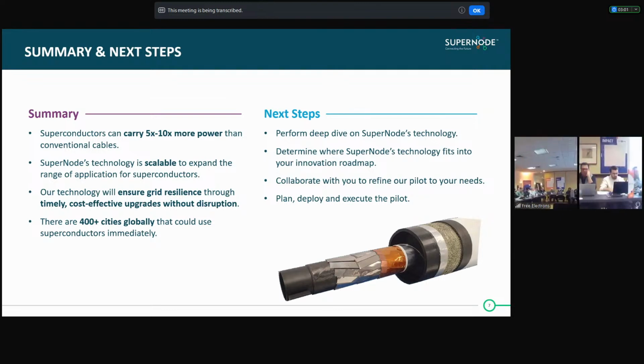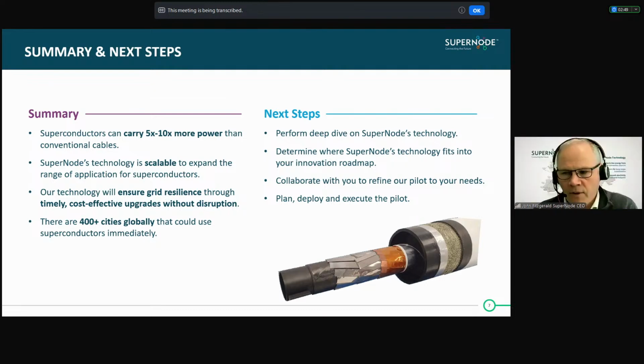Okay, and what will be the design then? Concentric with one cryostat and 3 separate cables? And voltage too, if you could say a few words on this. I'll invite Andrew Carlisle, our Chief Technology Officer, to answer that one. It depends really on the voltage levels. For something like 110 kV 3-phase, we'd propose a triad configuration, with 3 separate phases individually located inside the cryostat in a triangle configuration. At lower voltages, you can do concentric phases, and as you go up to very high voltages, the system needs to be split out into 3 separate cables.